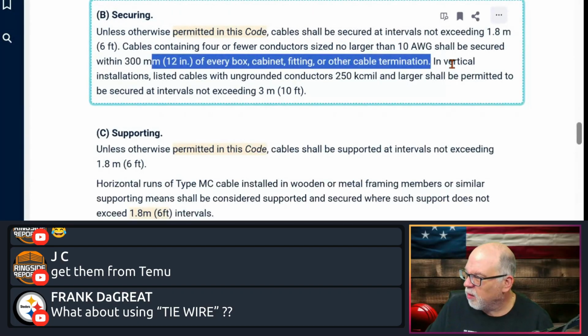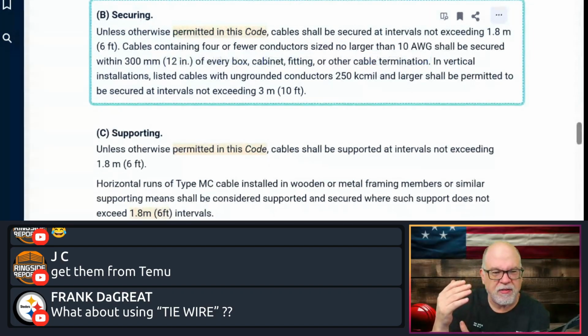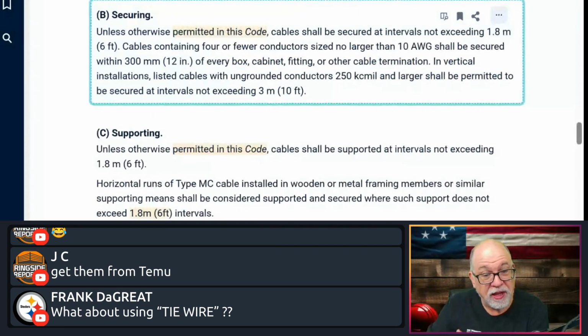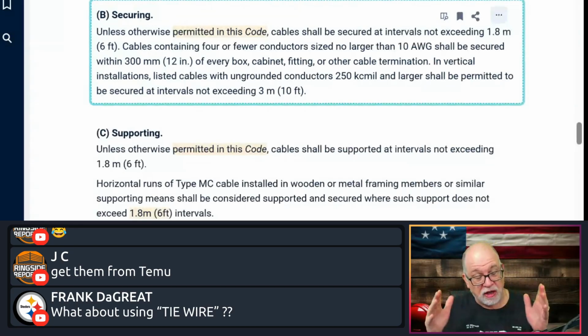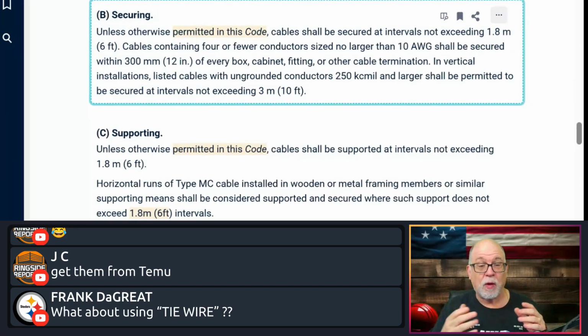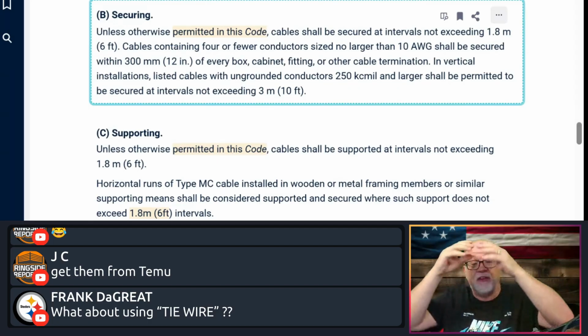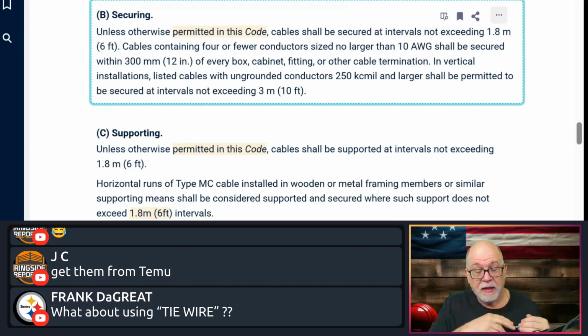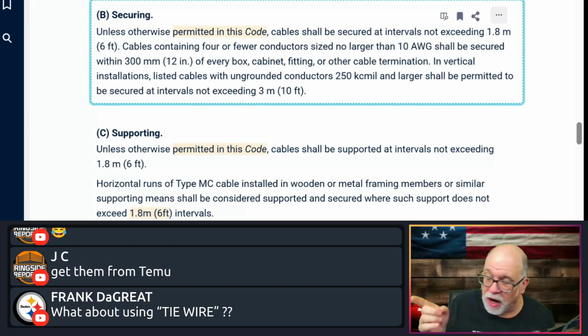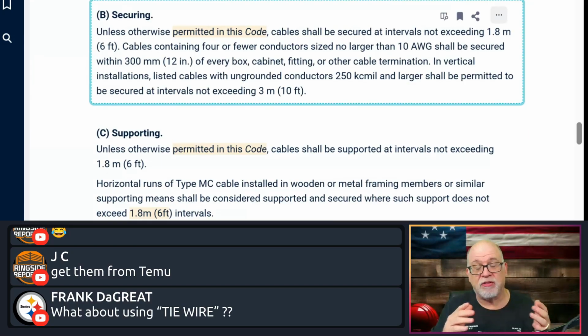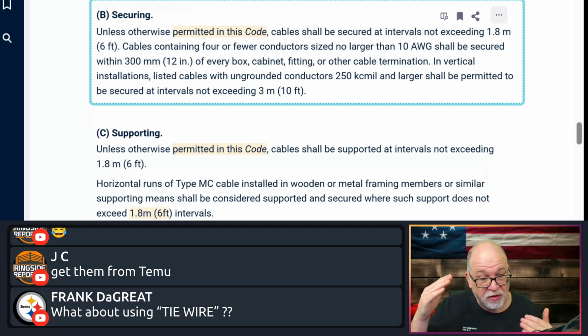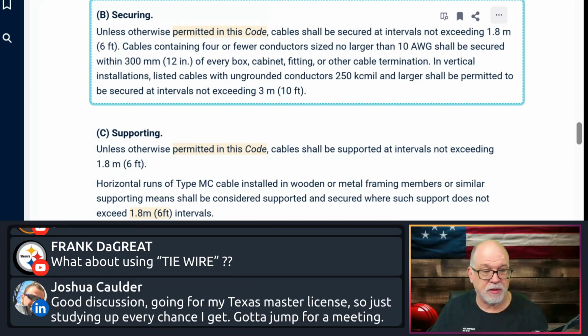However, okay, well, what does that mean? What if it's not? What if it's more than 4 conductors? Or what if the conductors are larger than 10? Well, then you follow the general rule and you secure it and support it every 6 feet. So this is why you may have some big MC with the 4/0. I'm just saying. It comes out and then the strap is maybe closer to 6 feet away. Why is that okay? Because the requirement to secure it within 12 inches only applies to the MC cables that have 4 or fewer conductors and the conductors are not larger than 10. Okay. So I could go up to 6 feet with larger MC. You hear what I'm saying?